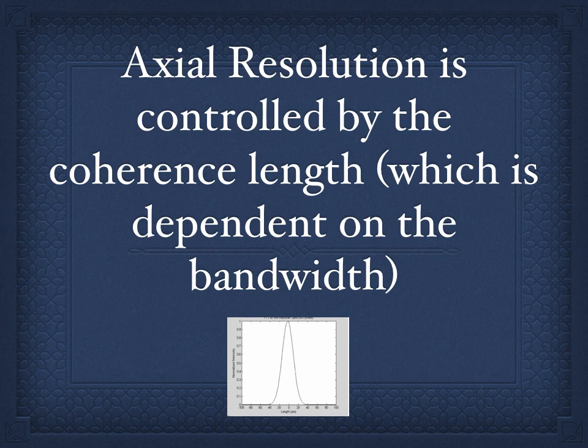The axial resolution is controlled by the coherence length of the source, the bandwidth of light, of frequencies within the light. When we're looking at a pulse, the pulse duration, where we measure the duration from isn't critical. Let's say we're measuring the reflection off of a mirror. A mirror would be an infinitely thin interface. But we're only going to see it to within the pulse width. That's the maximum resolution you can have. We refer to this when we measure the interference off of a mirror as the point spread function. It determines our resolution, it defines our resolution.